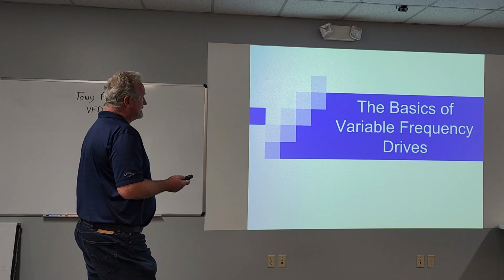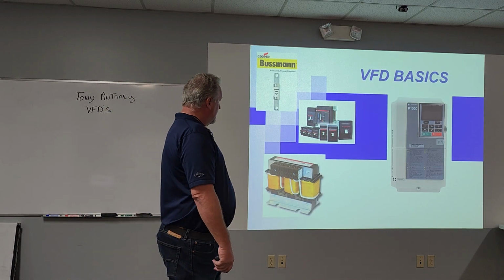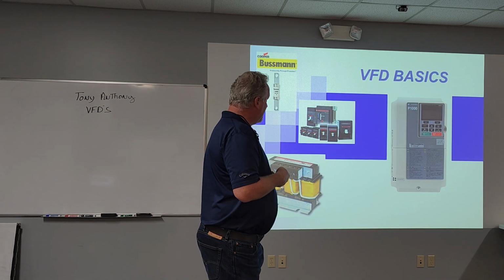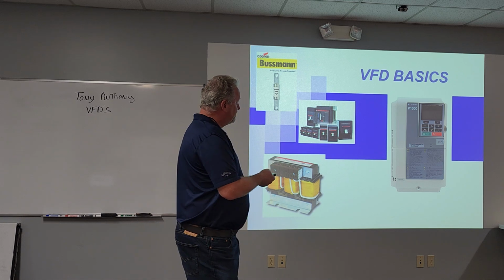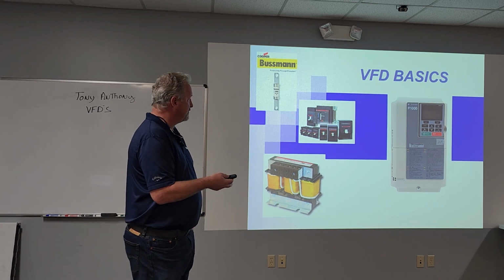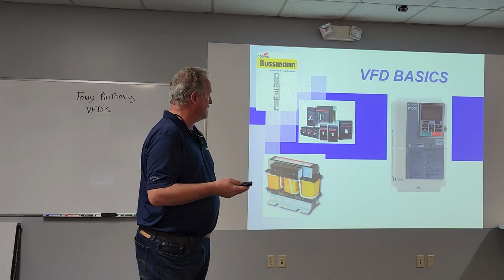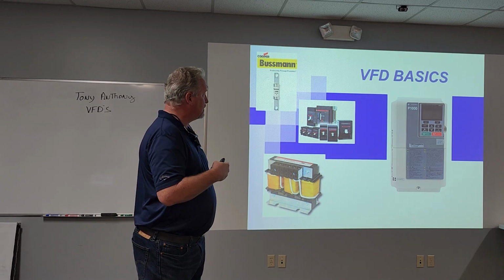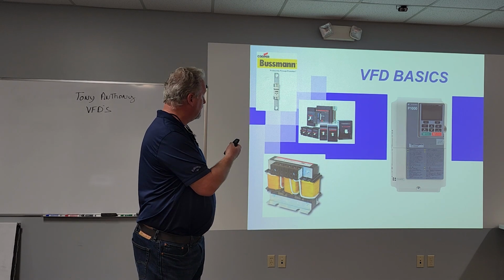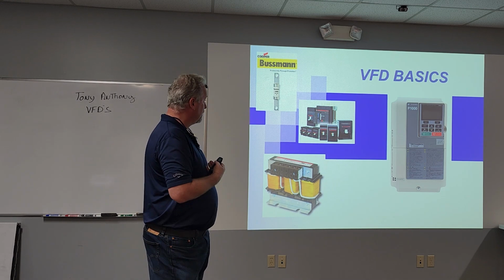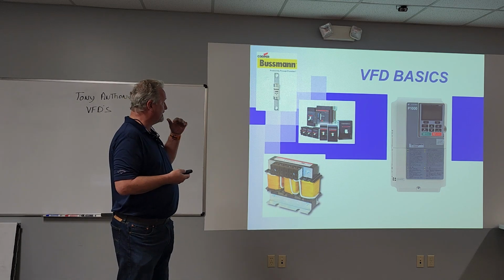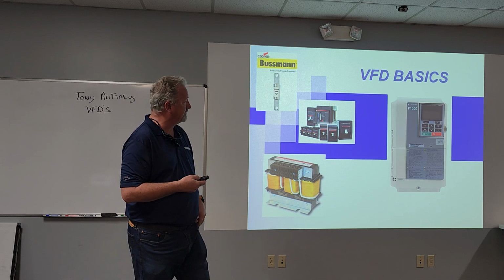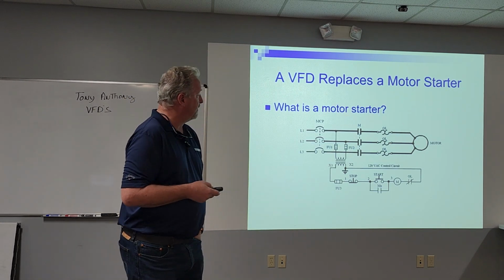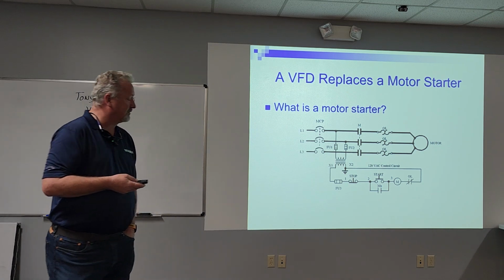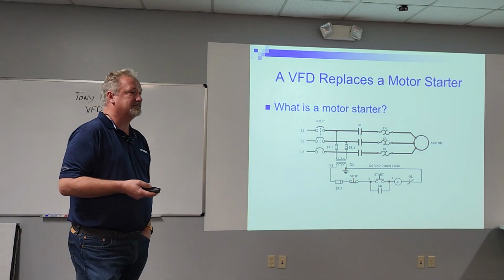So, starting with the basics. With a drive, this is our P1000, which is actually an industrial drive. All drives kind of work the same. And we're going to cover a little bit about what comes before the drive. We've got fusing, we've got line reactors, we've got breakers. First, before we get there, we're going to talk about what we're replacing, which is a motor starter.